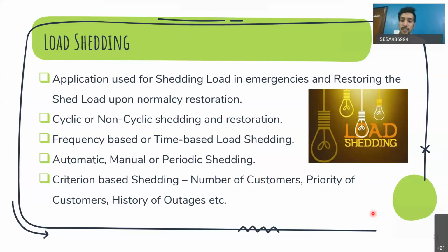Similarly, priority of customer. So for example, there could be a feeder with only 10 consumers, but 2 of them are hospitals, so they are very high priority. So even though the number of customers is less, because the priority is more, you shed them at the last. Maybe there is an opportunity that you have already achieved the requirement and you don't have to shed it. So that way they are put at the last.